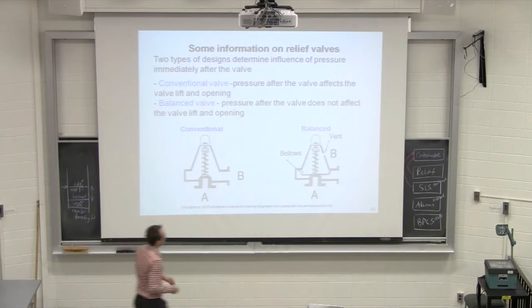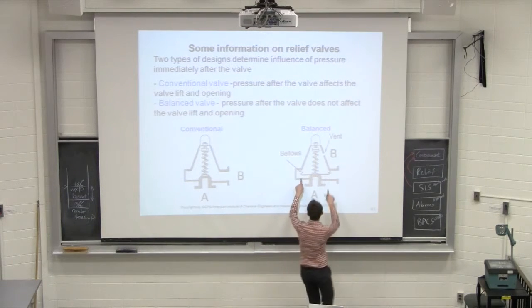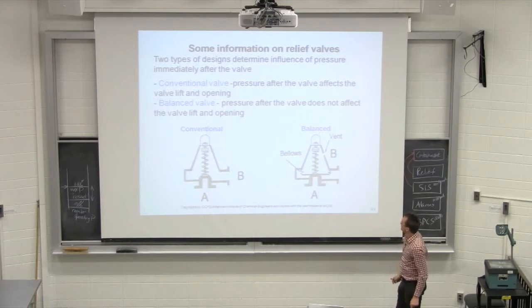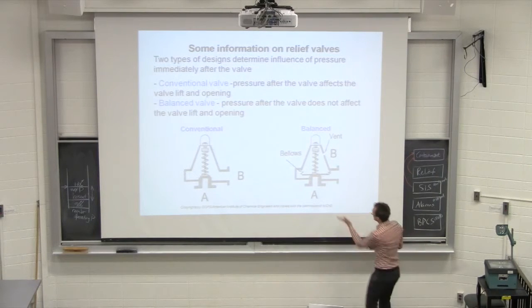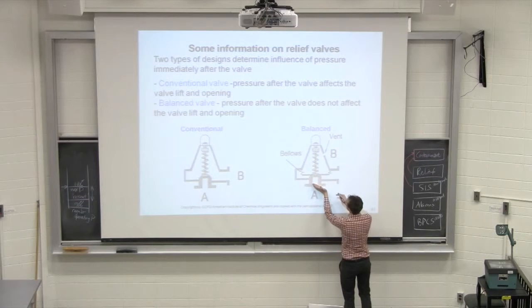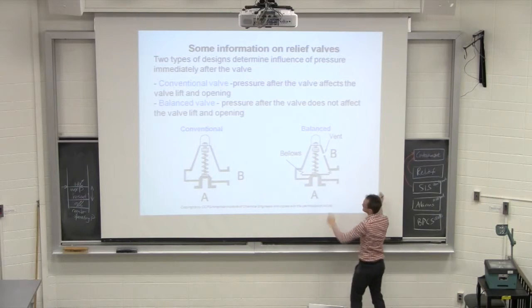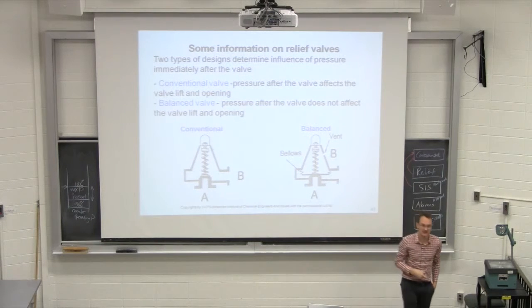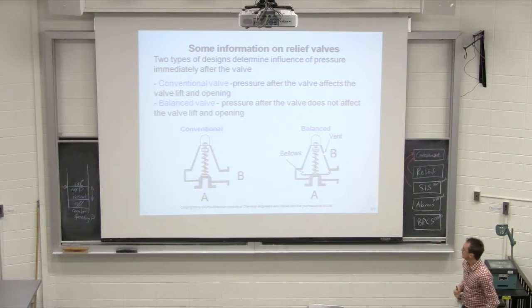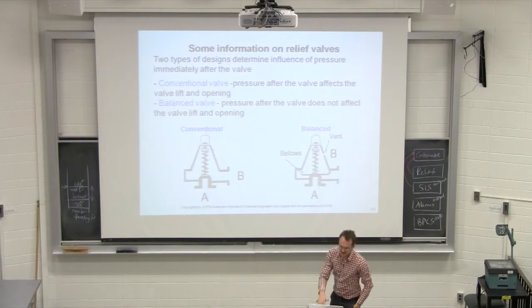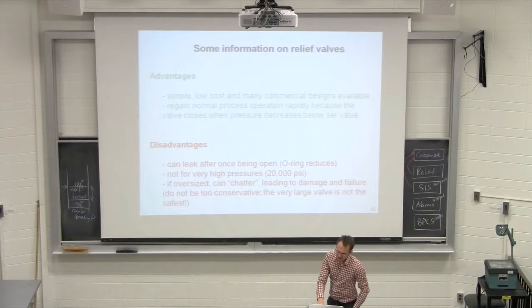So what we'll see then is a valve with this sort of accordion shape, a bellows, to partition the valve. And so when this lifts, you need pressure inside it to go somewhere, so there's an atmospheric vent. This will lift, but this prevents the back pressure from reaching the valve's working parts. So there's those two types of design for the relief valve.